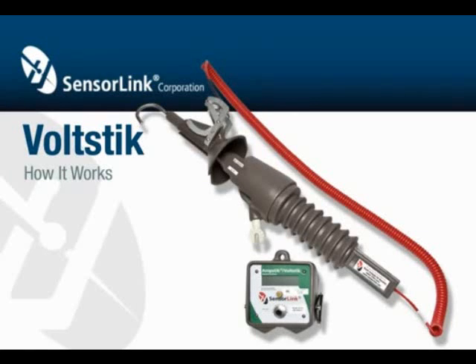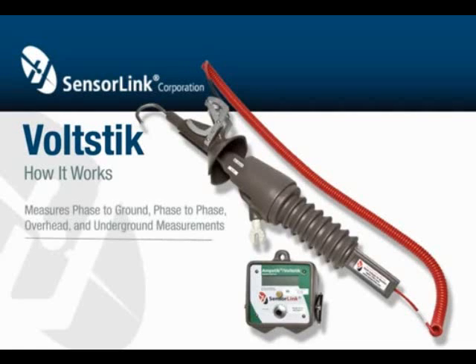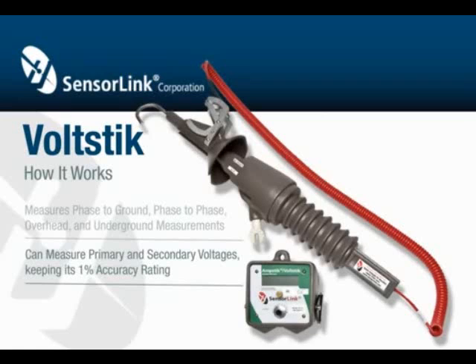The Voltstik is designed for measuring voltage anywhere on your medium distribution systems — phase-to-ground, phase-to-phase, overhead and underground measurements, all made by one man with one stick. The same meter can measure both the primary and secondary voltages and keep its 1% accuracy rating.